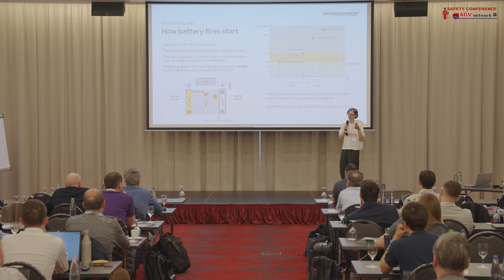Thermal runaway is a cell failure caused by cell overheating, and it can have both internal and external factors affecting it. When we talk about internal failures of the cell, we often talk about defects connected to the cell manufacturing processes. Those are addressed by quality processes, inspections, end-of-line testing.